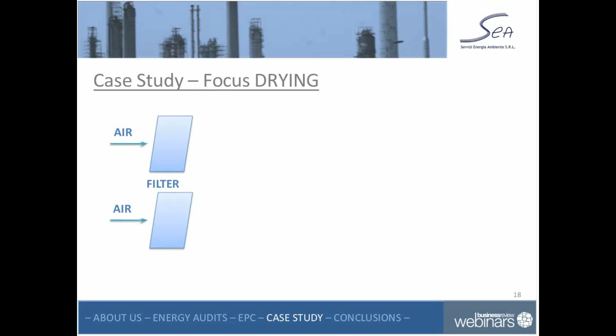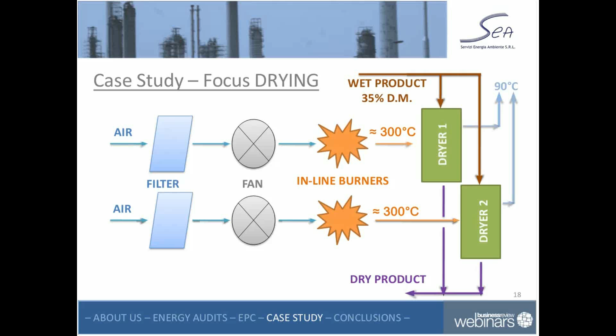But let's move on with the energy saving measures and focus on the drying process. We have two drying lines where air is heated up at 300 degrees and sent to a dryer. Inside the dryer it meets the wet product and is very well mixed, and at the bottom the dry product is recovered, leaving the dryer at about 90 degrees. It's very important to keep that 90 degrees at the exit of the dryer as a good measure of the drying effectiveness inside.